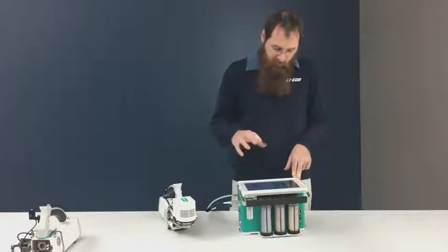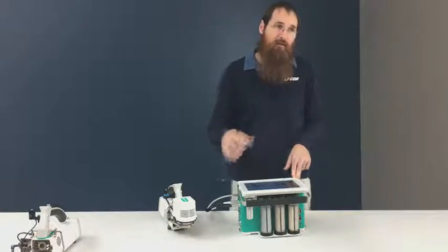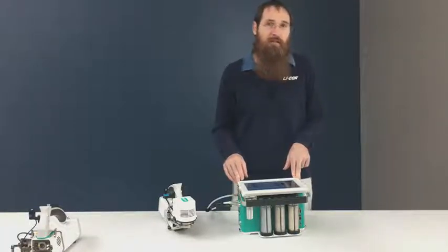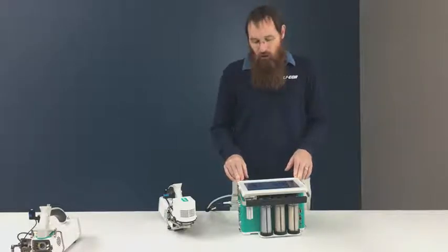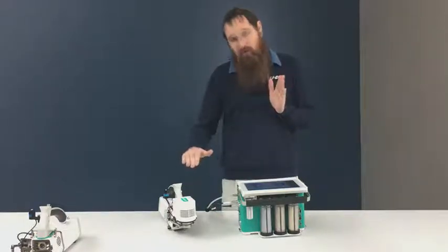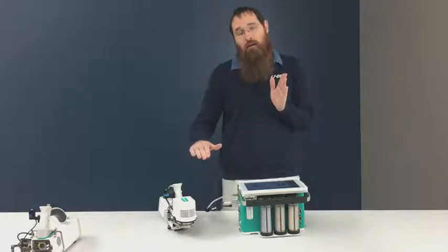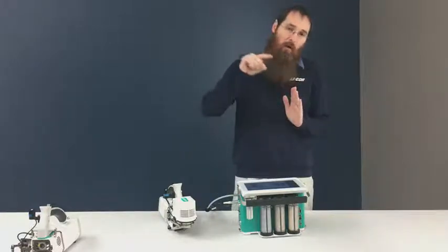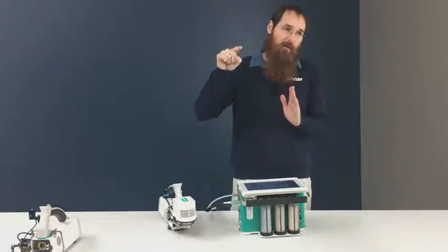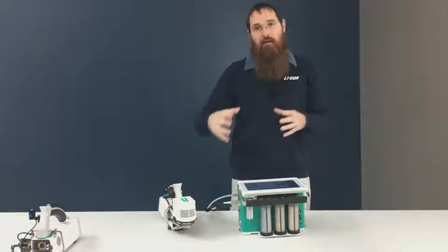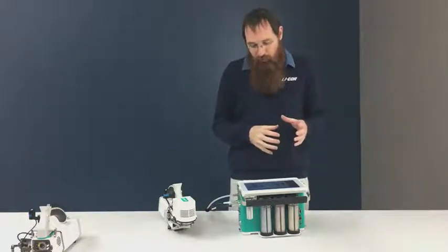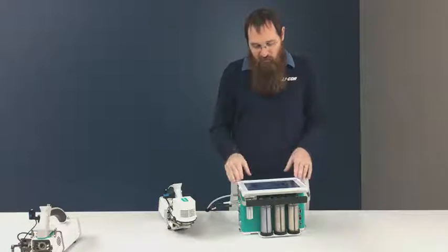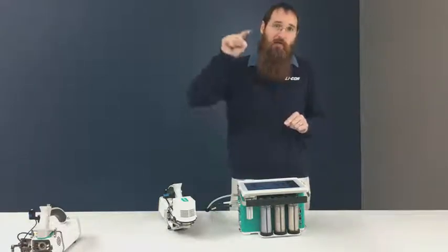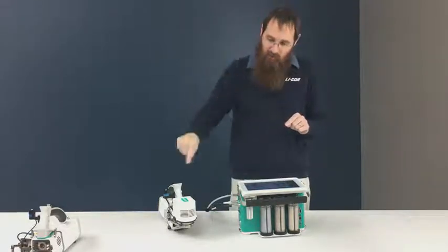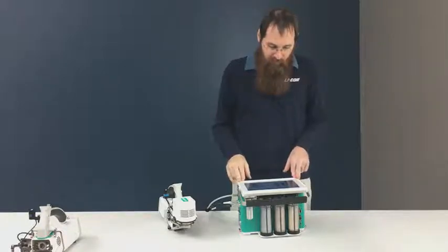A big difference between this instrument and the 6400 in the way that it controls CO2 is that the 6400 was very fast to go down in CO2 concentration, okay? But it was very slow to go up in CO2 concentration, and that was a consequence of where the mixer sat relative to the pump. On my 6800, it's just as fast to go up in concentration as it is to go down in concentration.